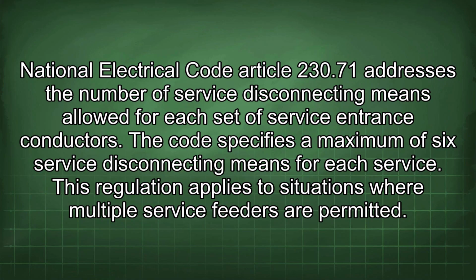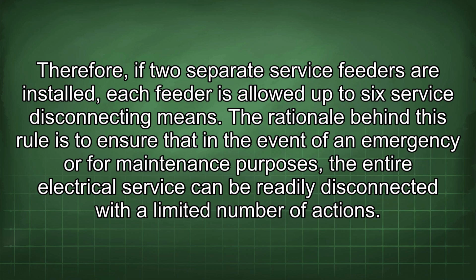National Electrical Code Article 230.71 addresses the number of service disconnecting means allowed for each set of service entrance conductors. The code specifies a maximum of 6 service disconnecting means for each service. This regulation applies to situations where multiple service feeders are permitted. Therefore, if 2 separate service feeders are installed, each feeder is allowed up to 6 service disconnecting means.